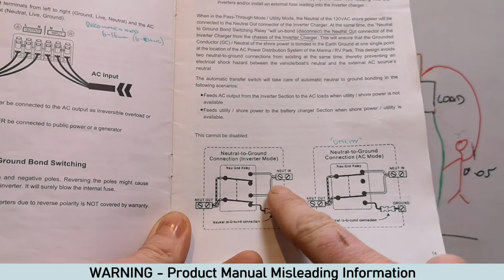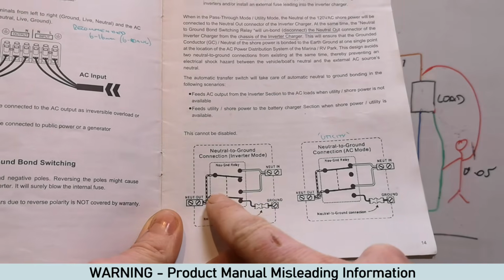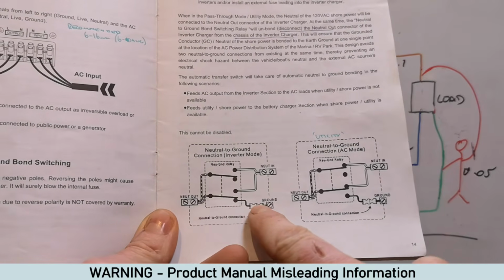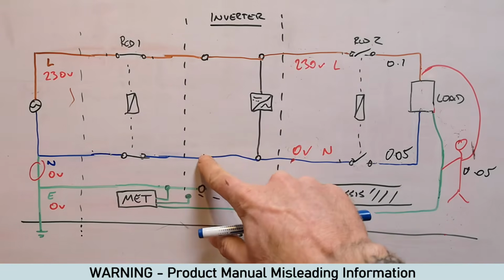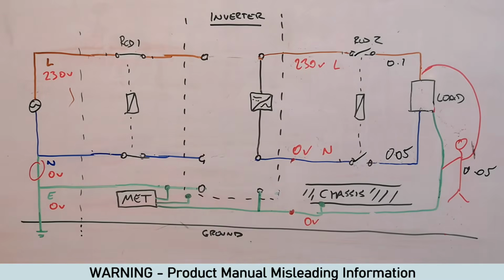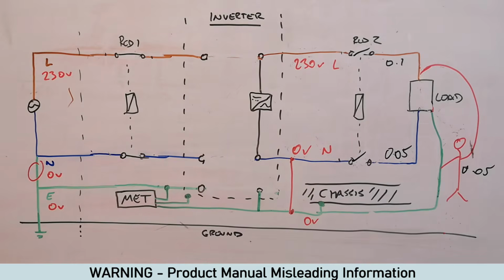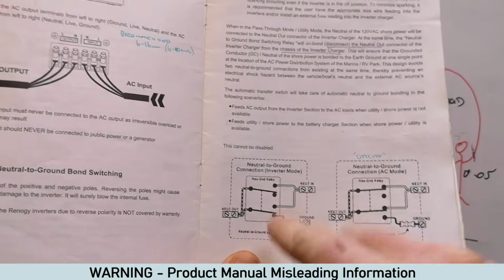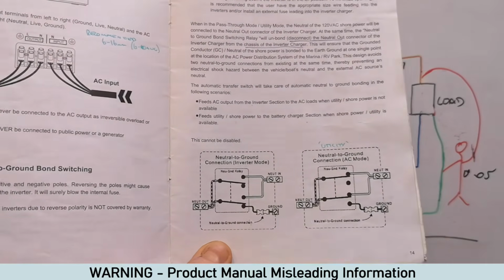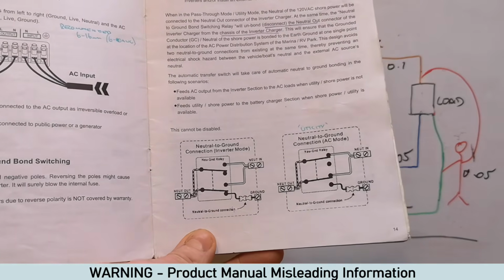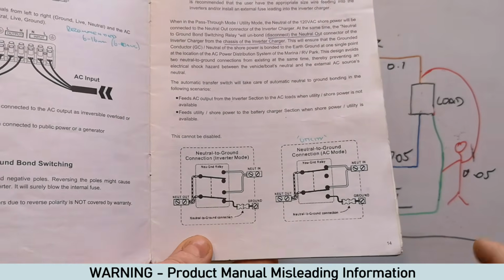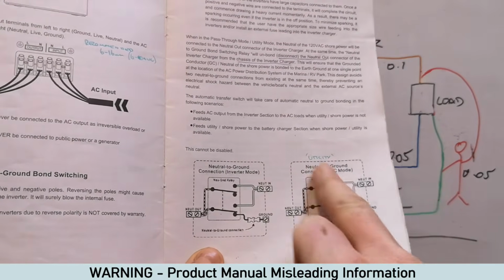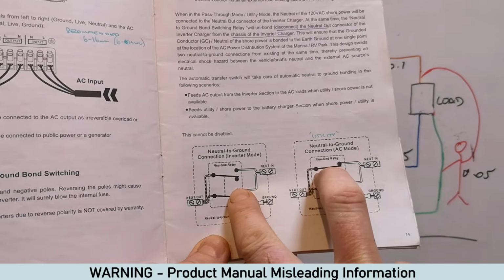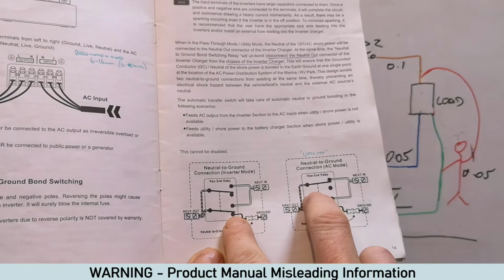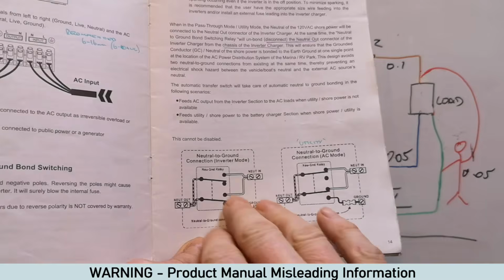So when switching to inverter mode, neutral in and neutral out get disconnected, as you can see there, and they link to ground. That would be the situation if we turn the power off there, introduce that link. However, when I installed it and tested it, the RCDs didn't work, and I was like, what's going on? I tested, the voltage was weird. Contacted Renogy, and they told me that this is not true. This is actually not installed in the inverter, and it's for the future. They're doing something in the future apparently with this.